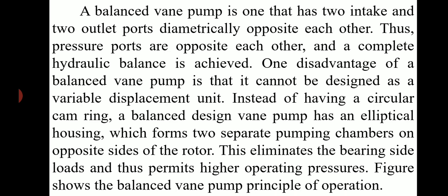Instead of having a circular cam ring, a balanced design vane pump has an elliptical housing which forms two separate pumping chambers on opposite sides of the rotor. This eliminates the bearing side loads and thus permits higher operating pressures. The figure shows the balanced vane pump principle of operation.